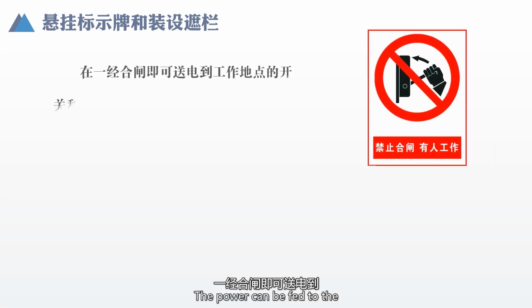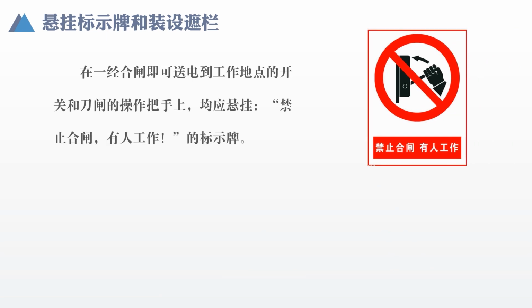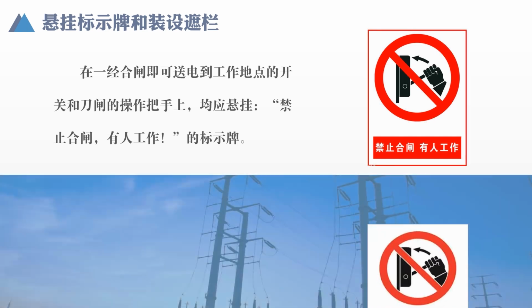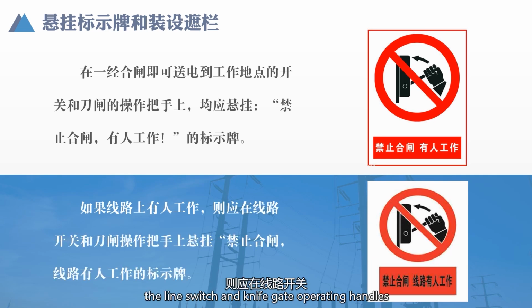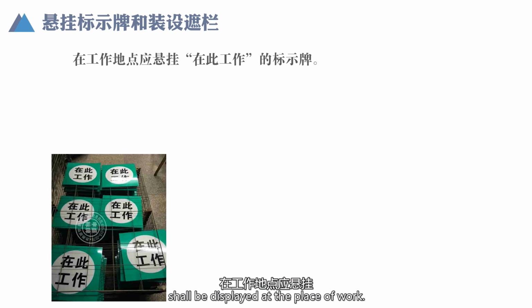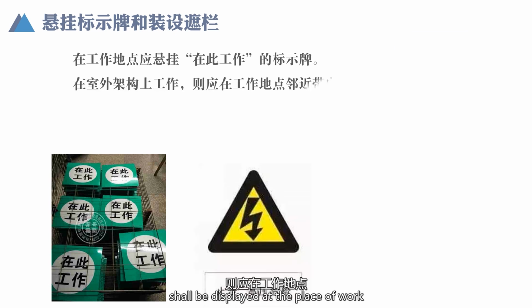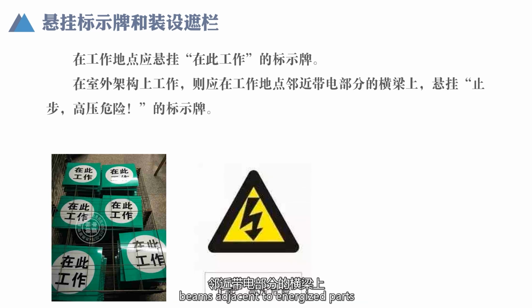The switches and knife gates at the workplace that can be fed with power, and the operating handle of a knife gate, shall be hung with a sign: Prohibition of closing. Manned work sign. If someone is working on the line, the switch and knife gate operating handles shall be marked: No closing. Line work signs should be displayed at the place of work. Work here sign. For work on outdoor structures, signs shall be displayed at the place of work, beams adjacent to energized parts: Stop. High voltage danger sign.